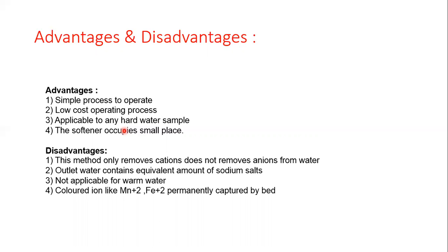But along with this, it has a lot of disadvantages. First, this method removes only the cations. It does not remove the anions from the water. The outgoing water sample contains the equivalent amount of sodium salt. That means again for the removal of sodium salt, we need a further process. This is not applicable to warm water because there is a possibility it may clog the material of your bed, and colored ions like manganese Mn2+ and Fe2+ get permanently captured by the sodium zeolite bed. Further regeneration is not possible.